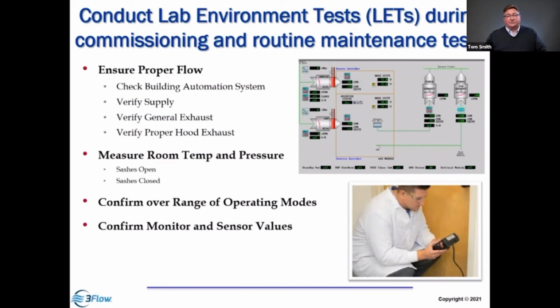And so our integrity is closely related to the accuracy and precision of our measurements. If we're not accurate and precise, we're going to be giving improper information upon which to confirm the calibration or to verify the proper operation. Now, we want to measure room temperature and pressure. If you've got a variable component in this system, with different operating modes, we want to measure it with sash closed and sash open, right? The flow through the room, if it's negatively pressurized, should be the same whether it's sash open or closed, because we still want to maintain secondary containment. So we make sure it has the right pressurization across that door, across the operating modes, sash closed, sash open, confirm it across the range, and then confirm that the monitor and sensors are reporting correctly.